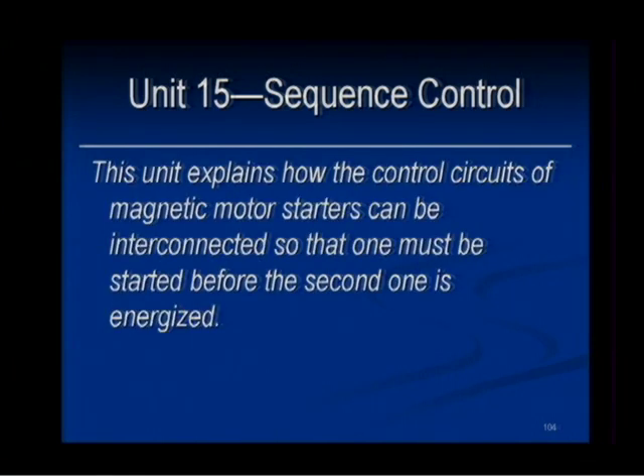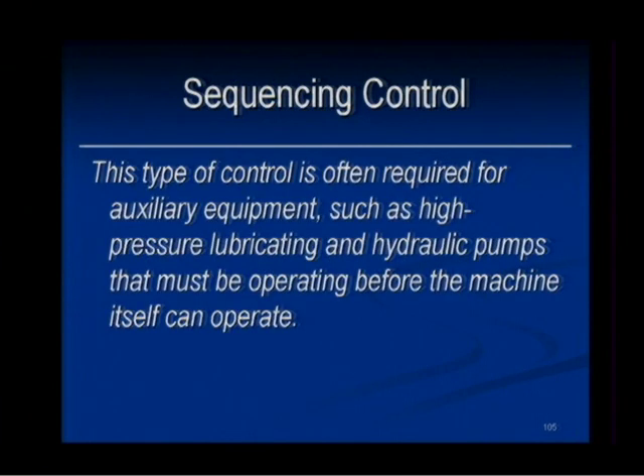This unit explains how the control circuits of magnetic motor starters can be interconnected so that one must be started before the second one is energized. This type of control is often required for auxiliary equipment such as high-pressure lubricating and hydraulic pumps that must be operated before the machine itself can operate.